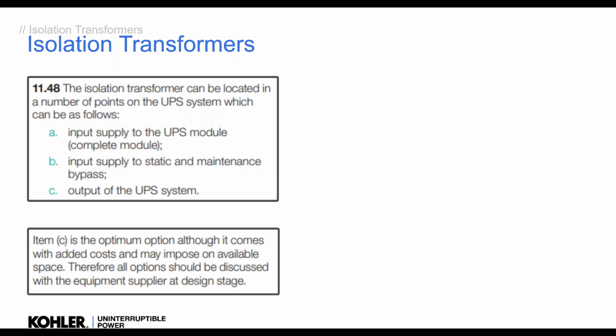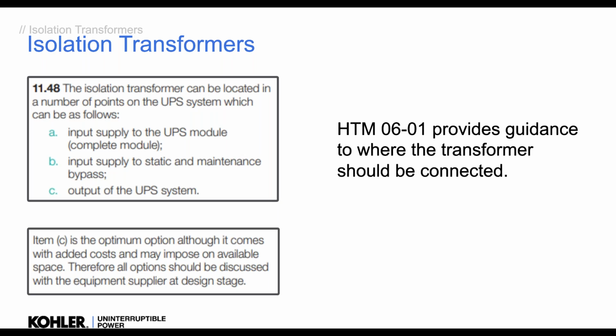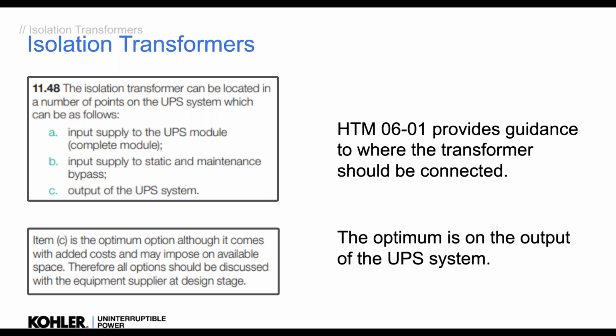And it talks about item C, on the output of the UPS, is the optimum option, although it comes with added cost and may impose on available space. Okay, it makes no difference. The cost is the cost. If you have a transformer on the UPS, it's going to add a cost. Sometimes actually putting it on the output could be cheaper because we can have a smaller one. Okay, and of course it does impose space, but it doesn't matter if you put it on the input, output, whatever, it still takes up space. Okay, but it's worth having a talk with the supplier about what's optimum. Okay, having it on the output is a good solution for various reasons, and we can have a look at it.